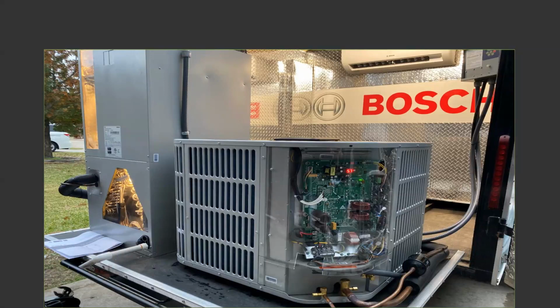Another feature that we have is actually a 2-speed blower board now, so that when we want to downgrade the blower in what we would call a Y1 situation, it does that. Y2, we speed up the fan motor. And we'll do that both in wintertime and summertime mode scenarios. A little bit different transformer. We've got a multi-tap transformer now. We have a fuse like your car fuse that's on the board at that particular time.